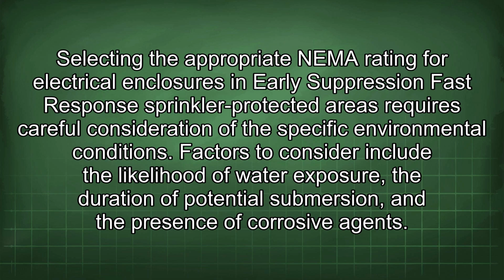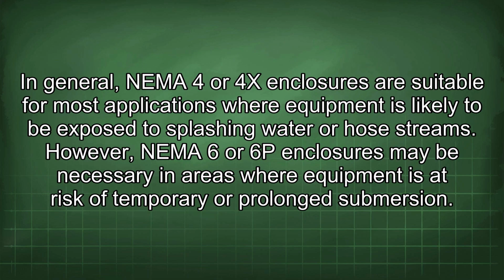Selecting the appropriate NEMA rating for electrical enclosures in early suppression fast response sprinkler protected areas requires careful consideration of the specific environmental conditions. Factors to consider include the likelihood of water exposure, the duration of potential submersion, and the presence of corrosive agents. In general, NEMA 4 or 4X enclosures are suitable for most applications where equipment is likely to be exposed to splashing water or hose streams. However, NEMA 6 or 6P enclosures may be necessary in areas where equipment is at risk of temporary or prolonged submersion.